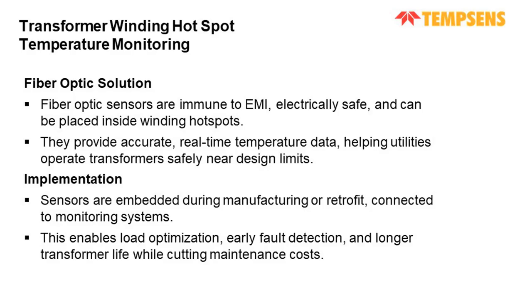How does the implementation take place? Typically, these fiber optic sensors are installed during the manufacturing process or retrofitted, with exact placement of fibers based on thermal simulation or industry standards like IEC and IEEE. So there are standards like IEC and IEEE that provide the best location for placing the sensors. They connect to a fluorescence controller unit, which feeds real-time data into the transformer SCADA or monitoring system.